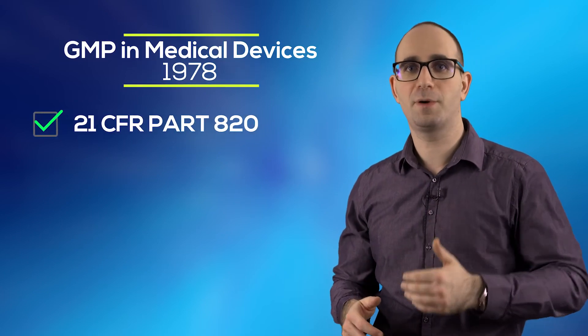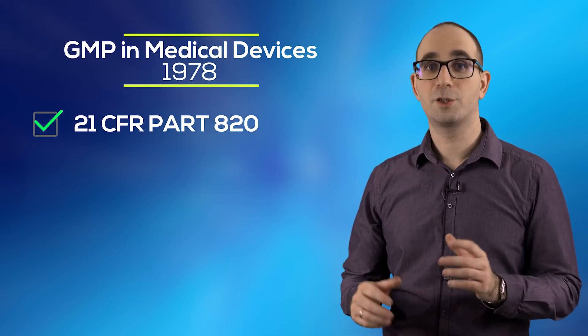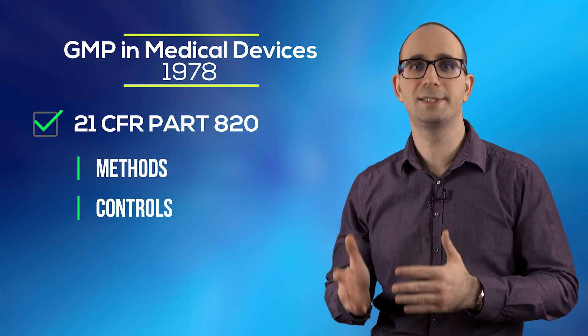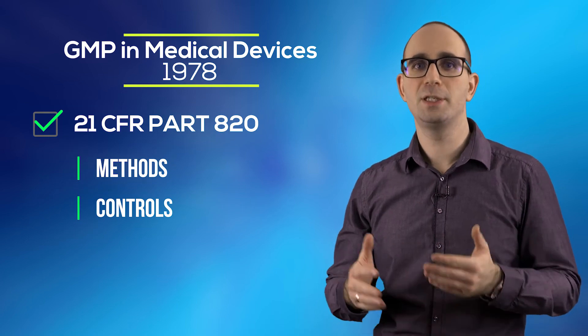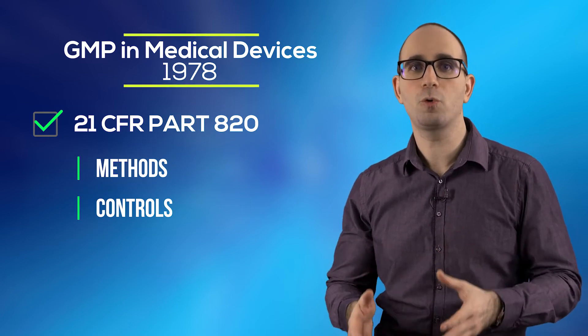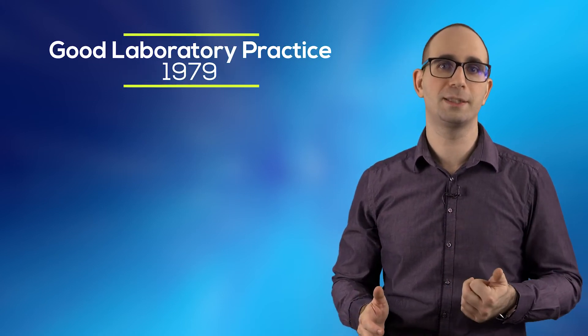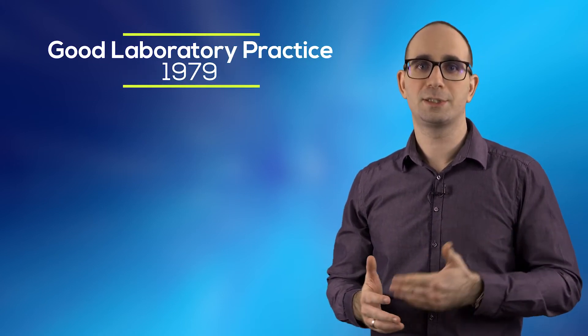Later in 1978 GMP for drugs was substantially revised and expanded to medical devices as well with 21 CFR 820. The regulations govern the methods used in the facilities as well as the controls used for the design, manufacture, packaging, labeling, storage, installation and servicing of all finished medical devices intended for human use. Not much later in 1979 the American government finalized the good laboratory practice, to regulate non-clinical laboratory studies for future potentially registered drugs.